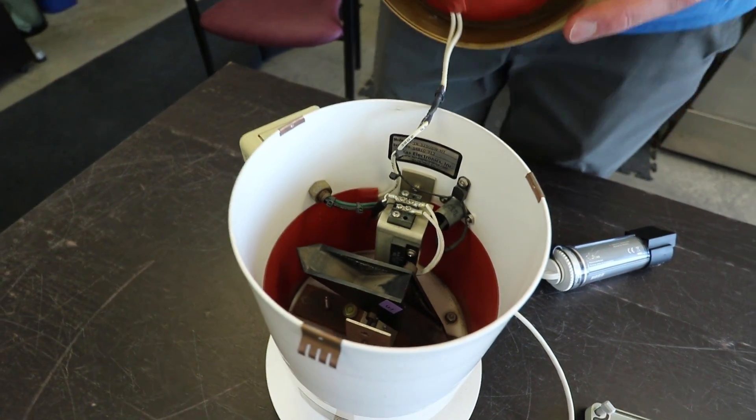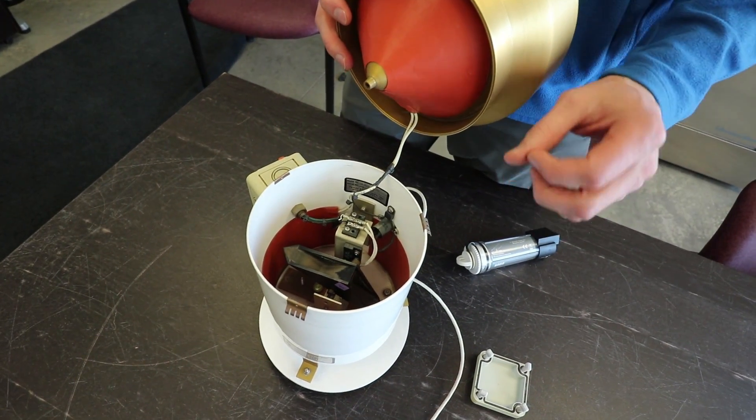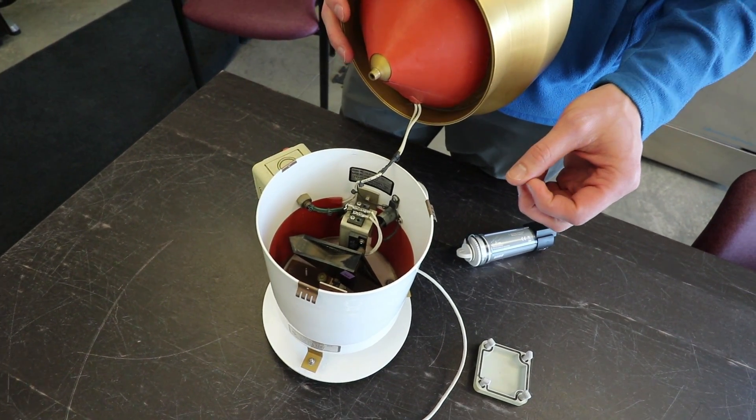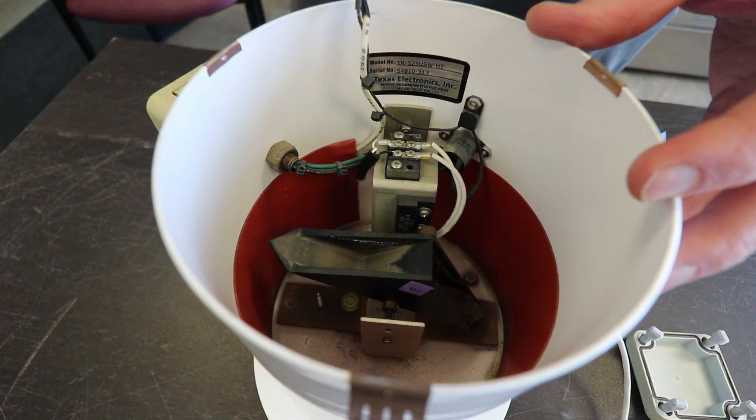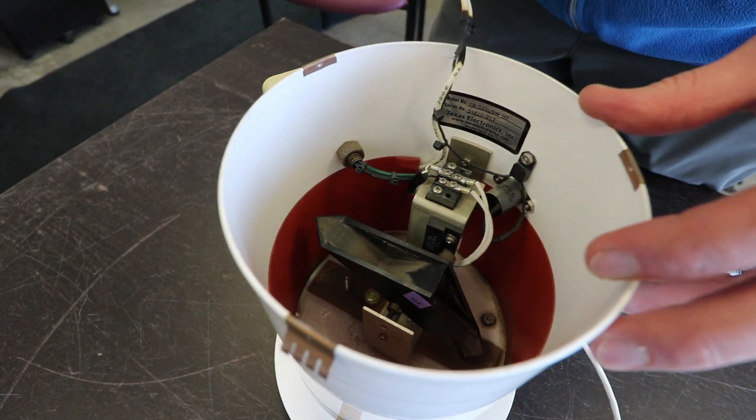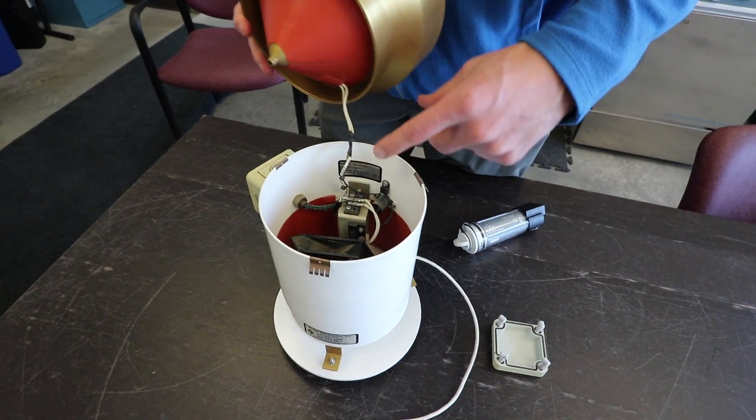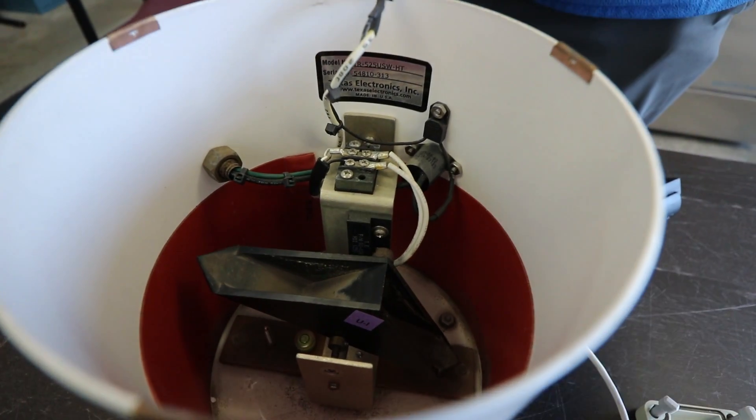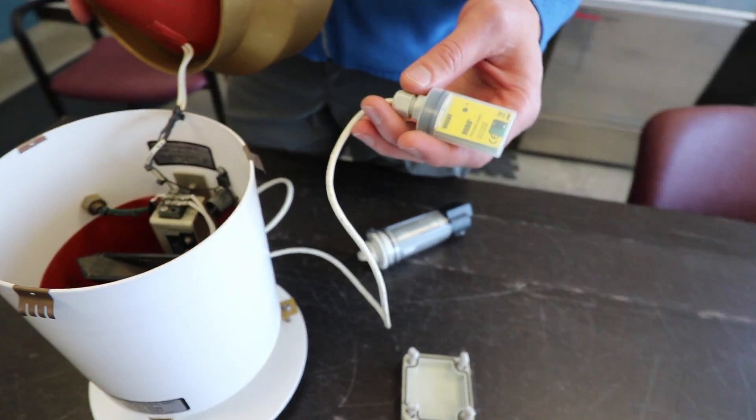Every time the tipping bucket tips, a magnet goes by a reed switch which creates a momentary contact closure, and that contact closure signal comes out through these two white wires and travels down this wire into a pendant data logger.